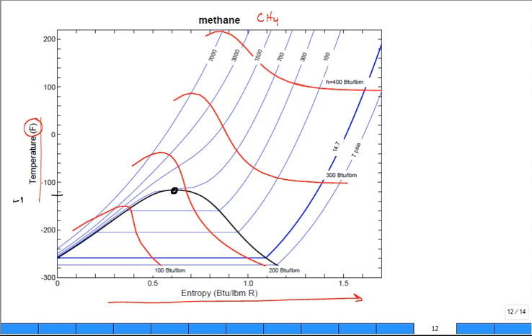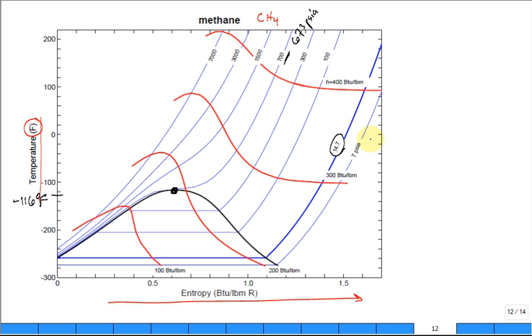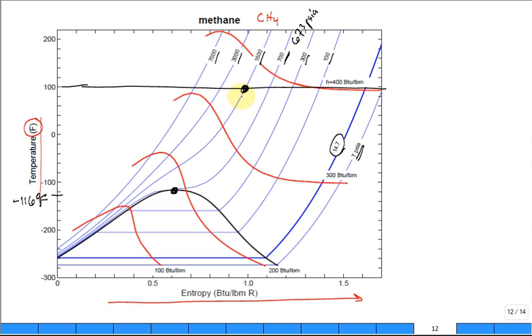The pressure is around 673 psia, right below the 700 psi line. The thick blue line is around 14.7 psia, atmospheric pressure. These are 100, 300, 700, 1500, 3000, and 7000 psi. The red lines are constant enthalpy. Let's say we have 100 degree F at some pressure, 1500 or somewhere in there, and you want to drop it down to this pressure. You're gonna follow a red line and you can see that temperature drop that would cause ice buildup.